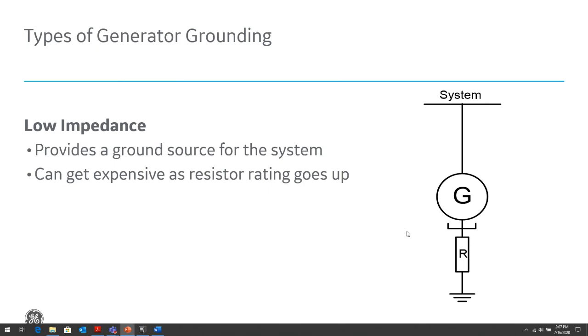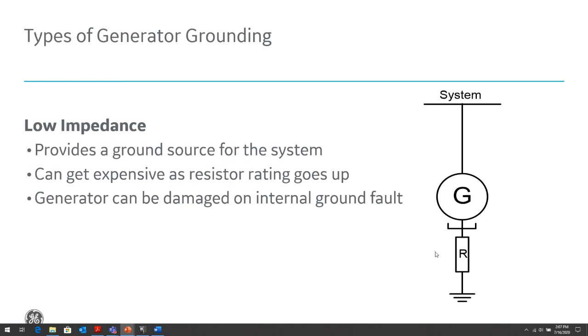Depending on the fault current level, it can be very expensive to install such a resistor, because if the ground fault is a couple of hundreds of amps, the I squared R rating goes up. So we need to have a higher rated resistance to be able to handle that. Also, because the generator is now susceptible to high levels of ground fault current, it can cause permanent damage to the generator. So it's basically between having to replace the generator or minimizing the damage so the repairs can be done on site, minimizing the outage time and the downtime of the generator.